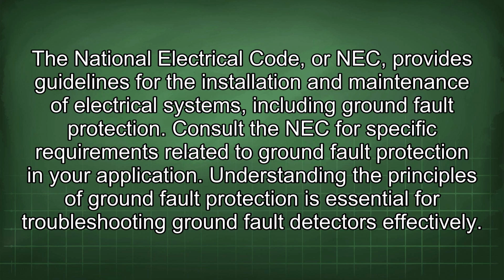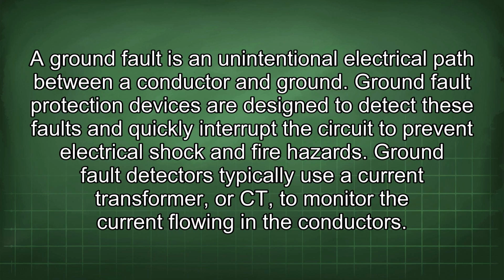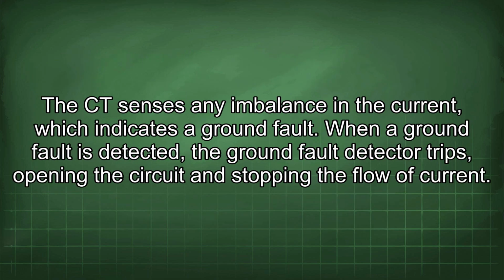Understanding the principles of ground fault protection is essential for troubleshooting ground fault detectors effectively. A ground fault is an unintentional electrical path between a conductor and ground. Ground fault protection devices are designed to detect these faults and quickly interrupt the circuit to prevent electrical shock and fire hazards. Ground fault detectors typically use a current transformer, or CT, to monitor the current flowing in the conductors. The CT senses any imbalance in the current, which indicates a ground fault. When a ground fault is detected, the ground fault detector trips, opening the circuit and stopping the flow of current.